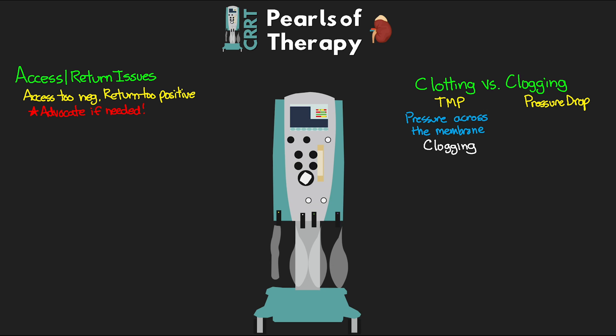If TMP hits a positive pressure of 350, it triggers an alert; above 450 triggers the alarm. This increasing TMP is measuring that the filter is clogging — as the filter clogs, those pores in the membrane fill up, requiring more and more pressure to move fluid across. Pressure drop, on the other hand, measures the pressure required to go through the filter — the change in pressure of blood entering and leaving the filter. The higher the blood flow rate, the higher the initial pressure going in. When pressure drop reaches 200 or higher, that triggers the alarm, indicating the filter is clotting.